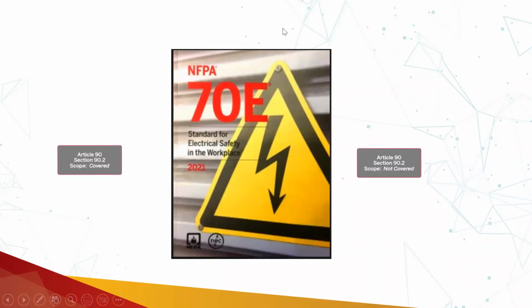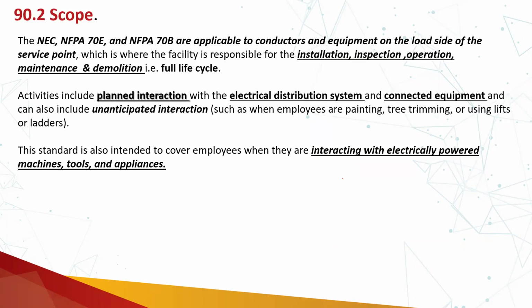But NFPA 70, because it is a US-based standard, you are going to find that in 90.2 they have specified that this standard can only be applied to the customer side of the installation, or towards the load side of the service point. So that means 70 is not applicable to the main equipment of the distribution, transmission, and generation industry. But if you are tapping some high voltage or bulk supply from 132 kV, from 11 kV, and that becomes the premises of the client, then 70 can be applied.